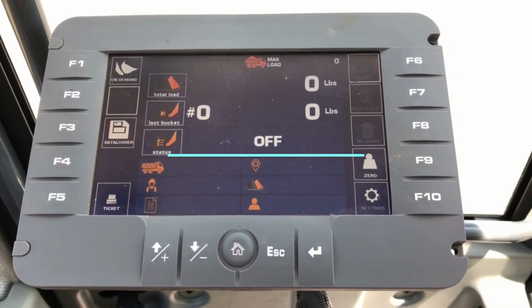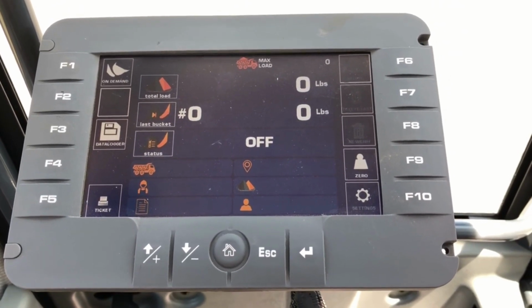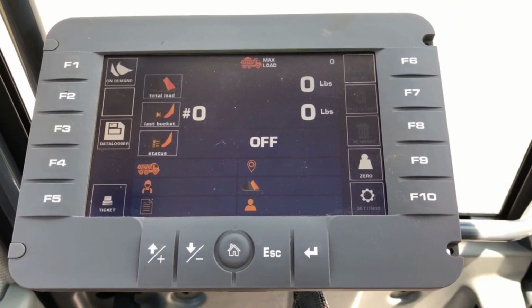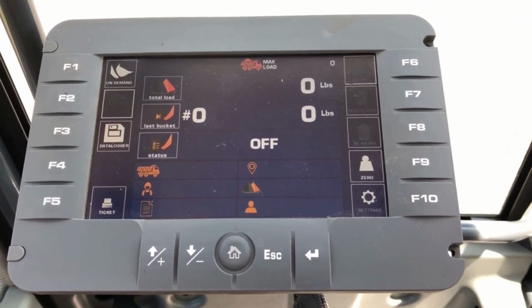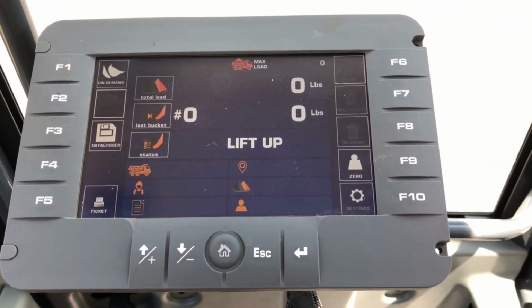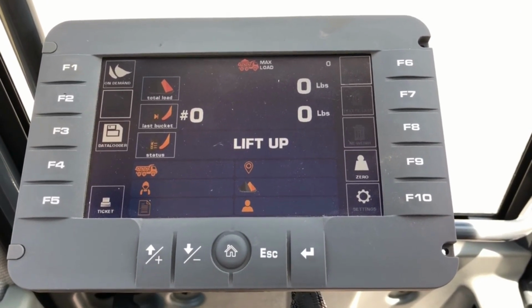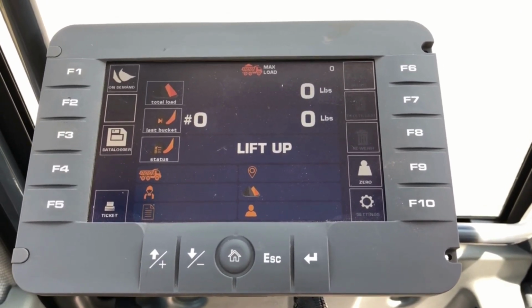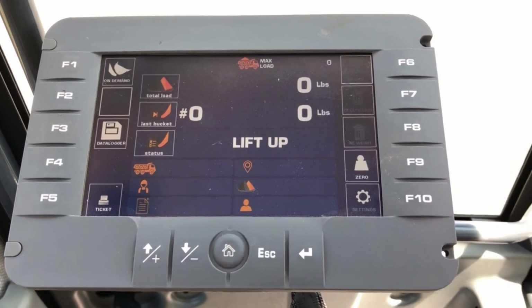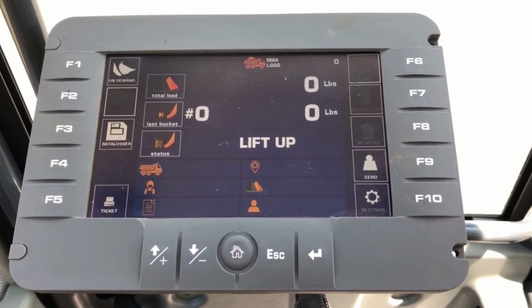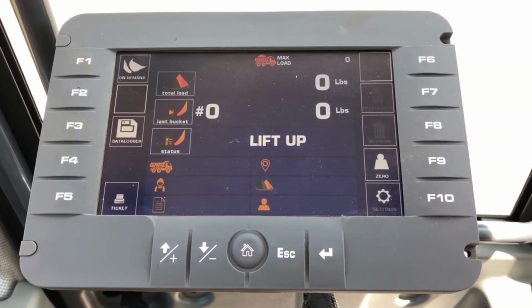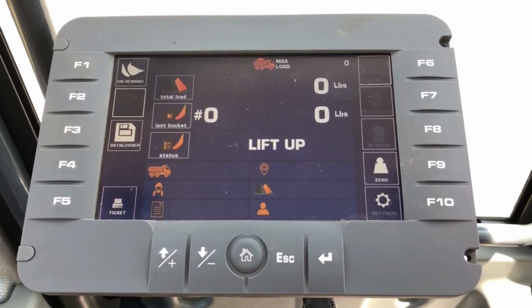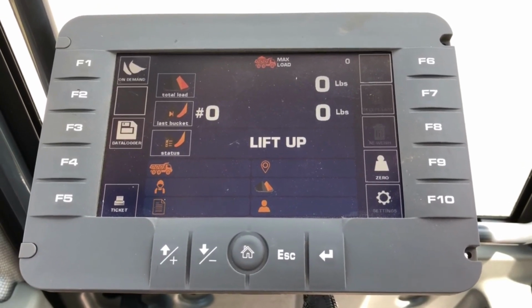This is how your indicator will look when it's first turned on. It does say off, so it's not in weighing mode right now. To get it to weigh mode, you need to just touch the home button, and then you'll see it change to lift up. You will need to calibrate your own scale for your machine. That is something we cannot do here at our shop. All machines are different, so you will need to calibrate it yourself.